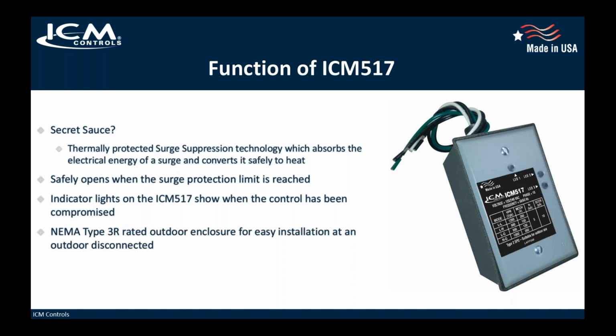If a spike comes down the line, we're going to suppress that spike within the ratings of the device, which is 100,000 amps and 1,020 joules. So it's a surge suppressor, exactly what it says. When a surge exceeds the limits of the device, the thermally protected fuses on the MOVs will open up and safely fail. Notice another thing: the box is a metal, NEMA 3R rated outdoor enclosure, meaning that any type of failure is going to safely fail inside that box.